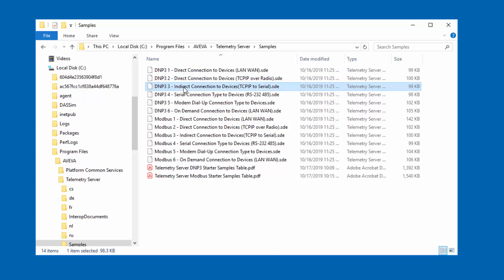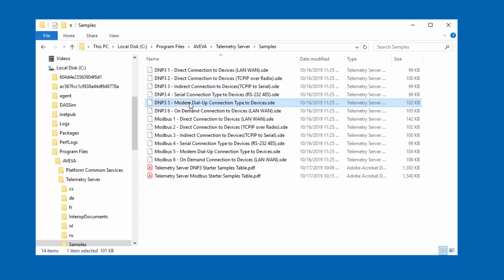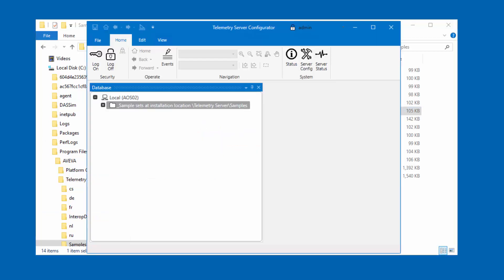As we move down the list, you'll see that we go from TCP over serial, if your devices are over Ethernet to serial bridge devices. If you're connected literally using serial com ports on your hardware, whether it's RS-232 or 485, you use this configuration. If you're using on-demand connections to the field devices, whether you're using modem or network, you will use the modem dial-up connection or the on-demand connection. I'm going to go ahead and import these configuration files. It'll take me a minute and we'll come back with the video once they are imported.